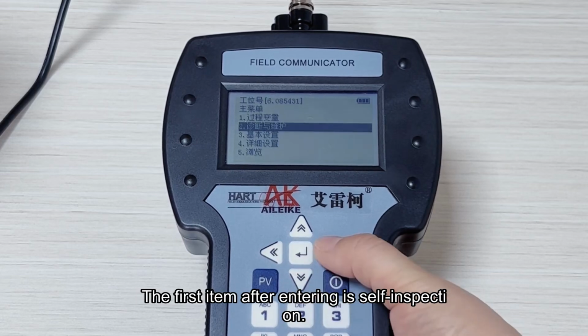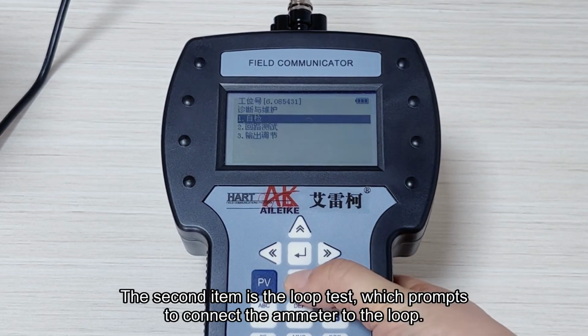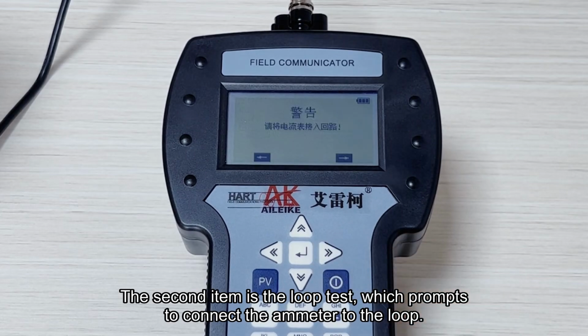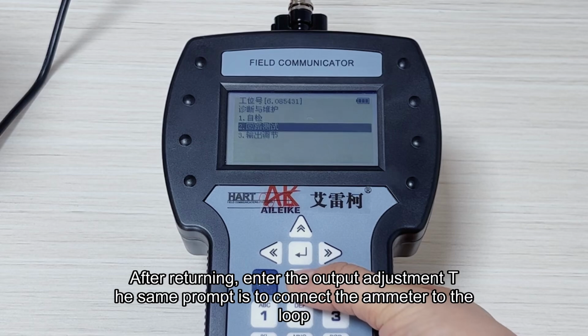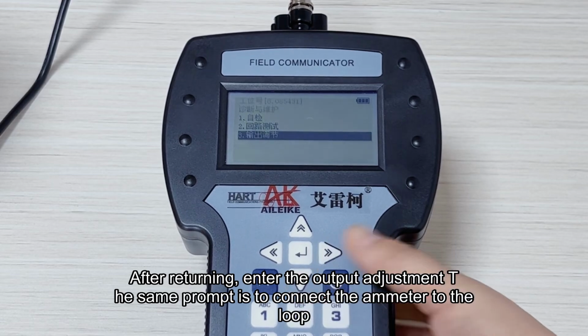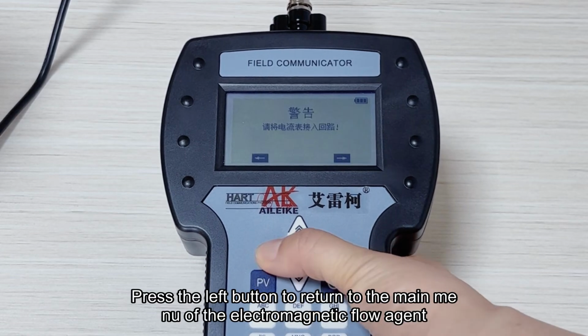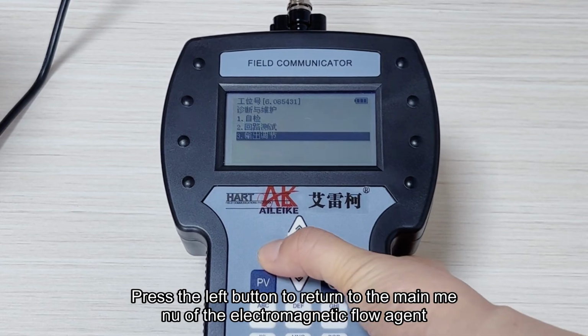The first item after entering is Self-Inspection. The second item is the Loop Test, which prompts to connect the ammeter to the loop. After returning, enter the output adjustment. The same prompt is to connect the ammeter to the loop. Press the left button to return to the main menu of the electromagnetic flow meter.